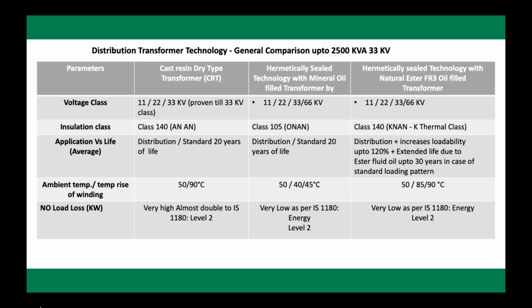When it comes to the other technology, which is something people call cast resin dry type, some people say resin cast dry type, somebody says encapsulated dry type, somebody says unfilled cast dry type, somebody says fully filled, and so much more. And this is nothing but again making copper windings and encapsulating them with the resins and hardeners, which come again from the petroleum family, the bisphenol families, and those resin and hardeners put together. It's just like the same Araldite we use in a house. A similar material is used to encapsulate this transformer, so the windings are protected from the outside environment. But all these encapsulations and impregnations do add combustible materials into it, and those also burn at a certain temperature.